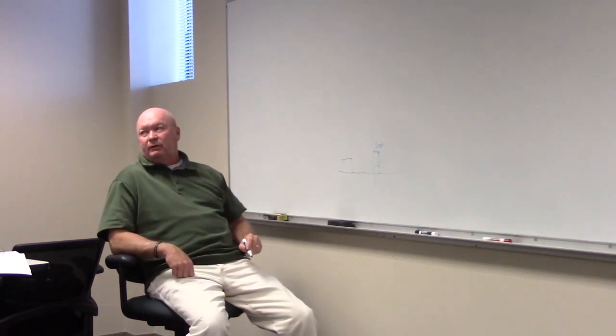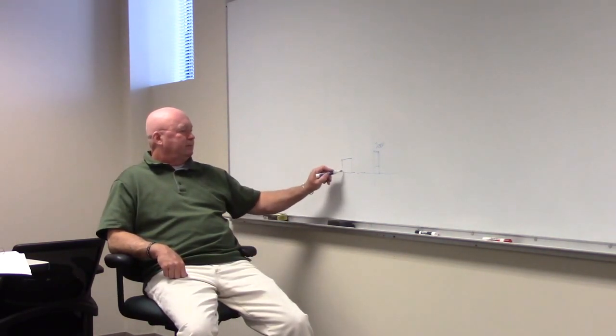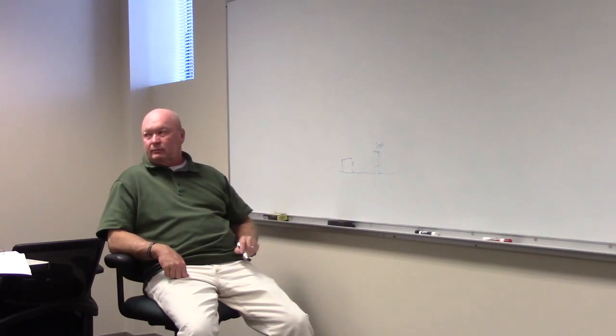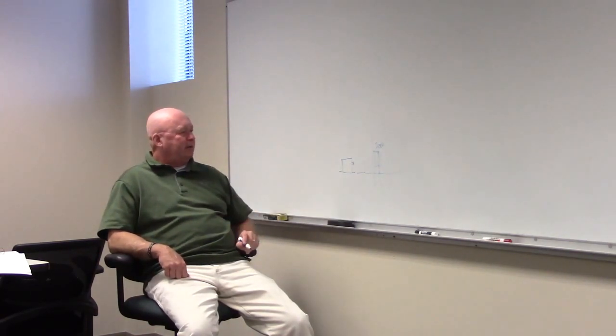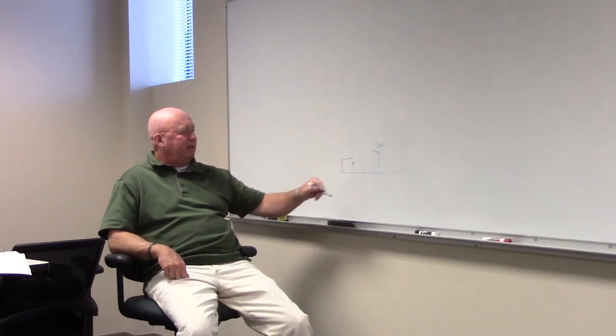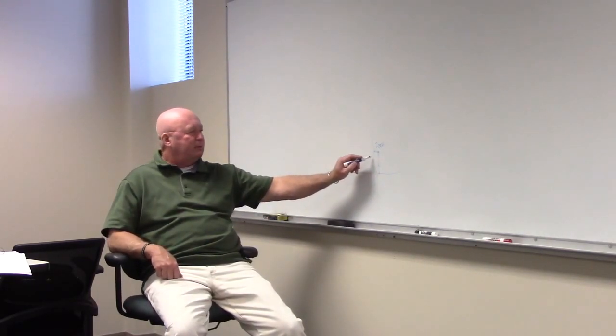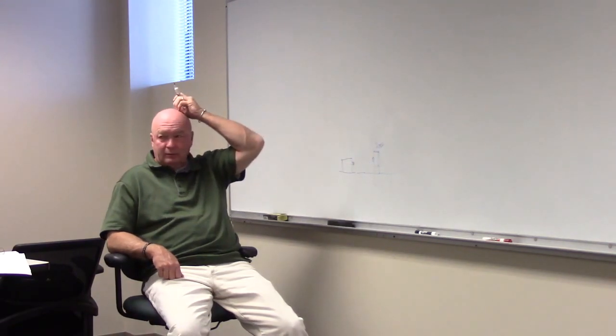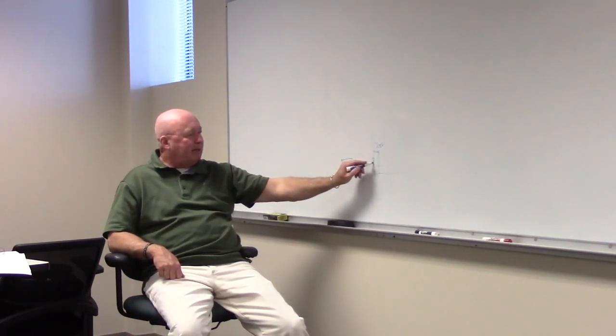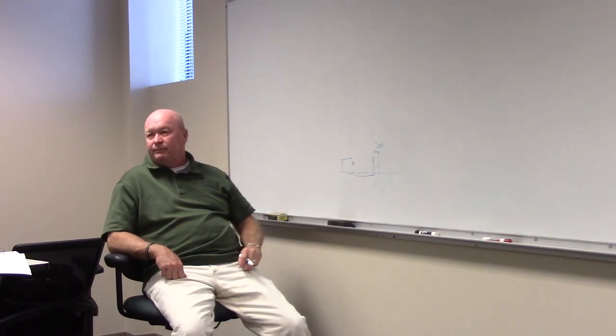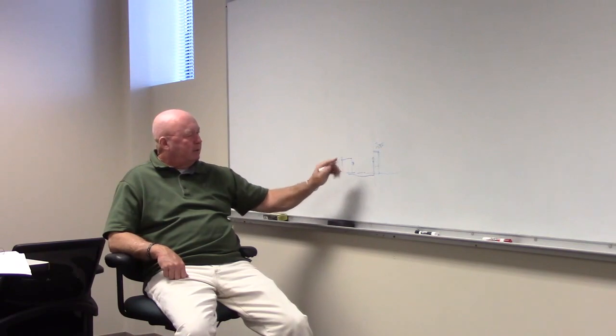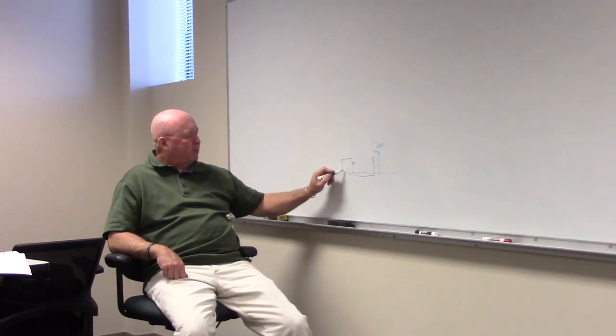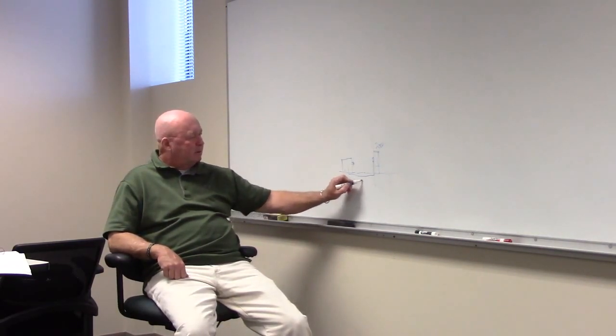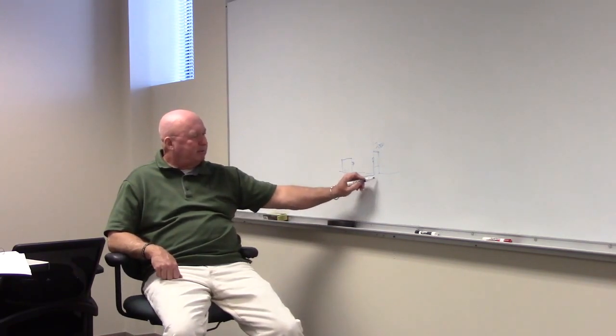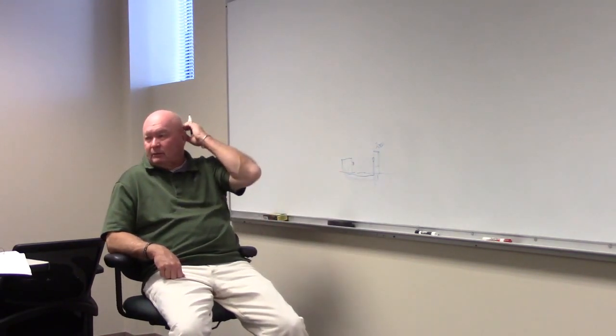Where's the meter probably gonna be located? On the transformer. Yeah, on the transformer, isn't it? Okay. Means nothing we gotta do there. Let's say they decide to put the meter on the building, which sometimes happens, then what must we do? Put it directly behind it. We gotta take a 1-inch pipe out of here and get over to the transformer, don't we? But if that's not there, either way, it doesn't matter. And then with our transformer, we're gonna have service wires, aren't we? Now notice we're underground. And so we stay underground and we come up inside the building and there's no main needed there, is there?